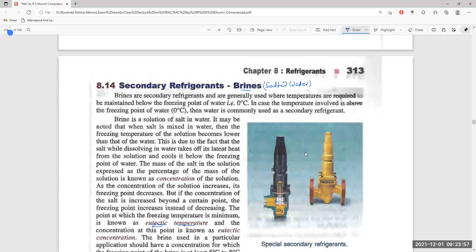The brine used in a particular application should have a concentration for which the freezing point of the brine is at least 5 to 8 degrees lower than the brine temperature required. Say a certain brine temperature is demanded by the system. The freezing point should be at least 5 to 8 degrees less than that desired brine temperature, so the amount of salt present in the brine should be such that its freezing point will be lower than the temperature desired for the system.